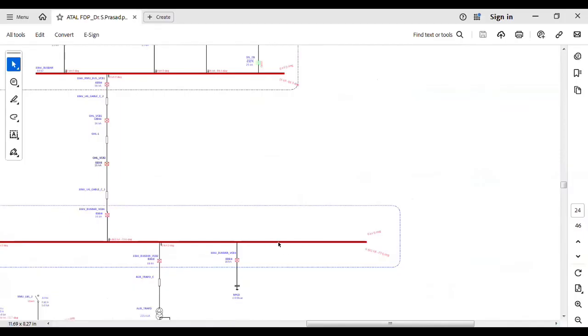Because we also need to see what is the bus bar short circuit withstand capacity. Bus bar rating also you have to check. Whenever you are going for an aluminum bus bar, what is the short circuit rating? Suppose a three-phase short circuit, a line to ground fault, or a double line to ground fault happens, you need to check whether the fault current exceeds the short circuit current capacity of the bus bar. Otherwise it will damage the bus bar. So therefore we are conducting the short circuit test to verify the rating of the bus bar, the rating of the circuit breaker, and the ratings of the line cables and all.